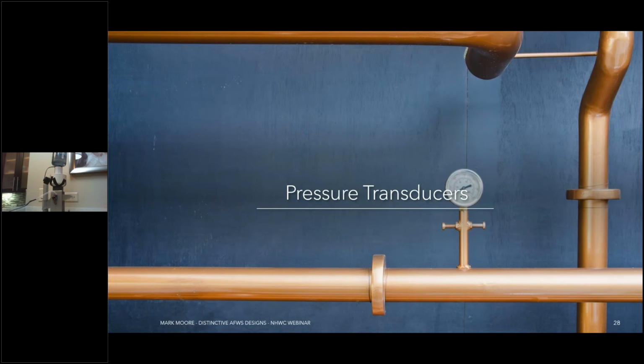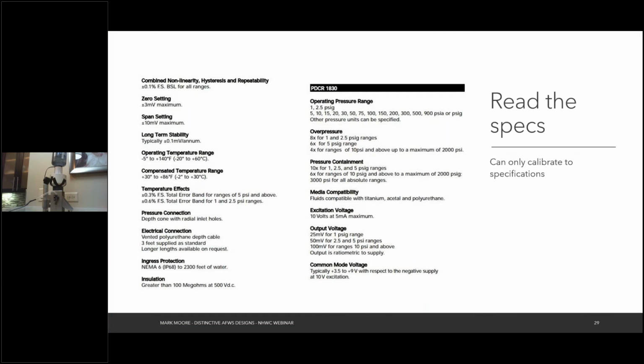So while this keeps going, we're going to take a quick step to talk about pressure transducers as well, because those are the other things we typically calibrate in this field. And I just said this, but we're going to read the specs, because we can only calibrate to specifications. Again, I pulled this off of a website for this pressure transducer, and this is a fun one to say. The combined nonlinearity, hysteresis, and repeatability is plus or minus 0.1% FS BSL for all ranges. Boy, that makes sense, right?